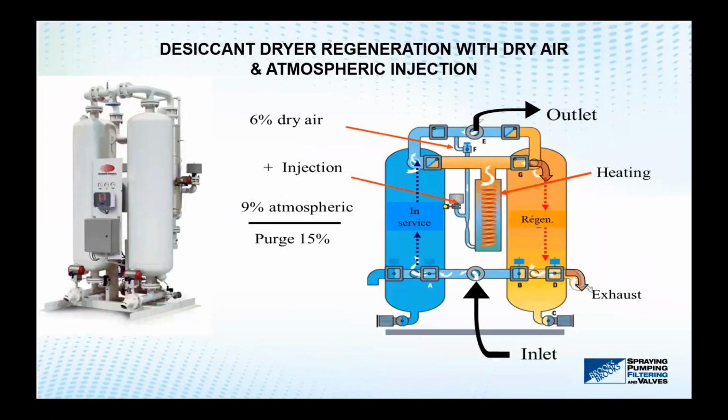The next design concept that we have here, I sort of call almost like a hybrid system. You're using 6% of your compressed dry air to do the regeneration. That would be similar to a heatless dryer where you're using 15%, but in this circumstance, you're only using 6%.